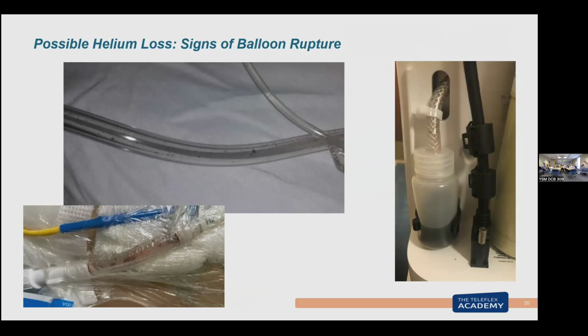The biggest problem, when you have blood in the tubing, is we don't know how much blood is inside that balloon. If I leave it in, let's say it's still pumping, the problem is that helium going past a clot inside of a balloon crystallizes that clot. So now when you try to remove it, it's stuck. That's an entrapped balloon, and you now have to take that person to the OR and get that balloon out.